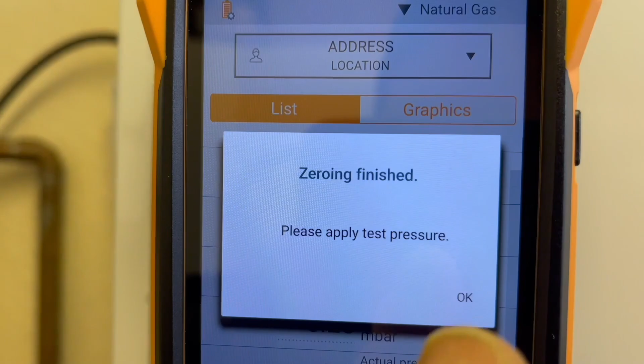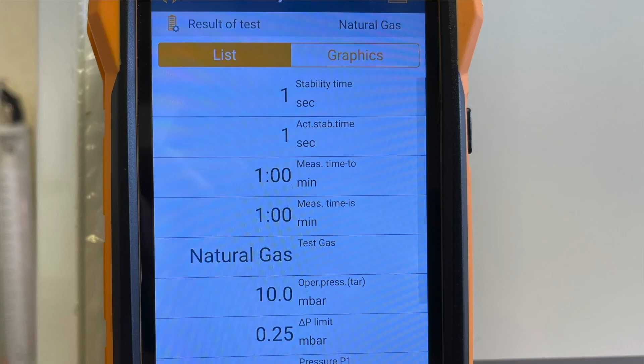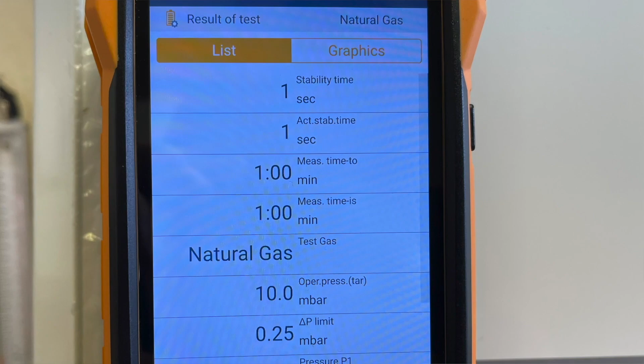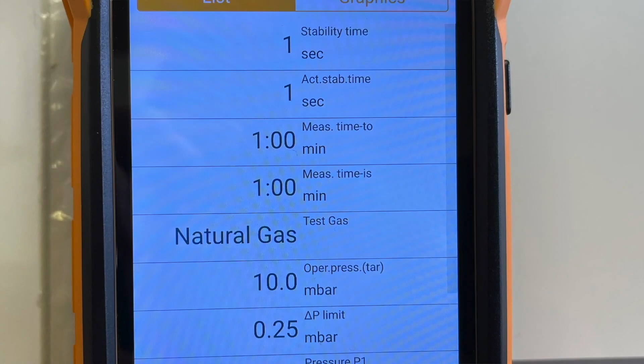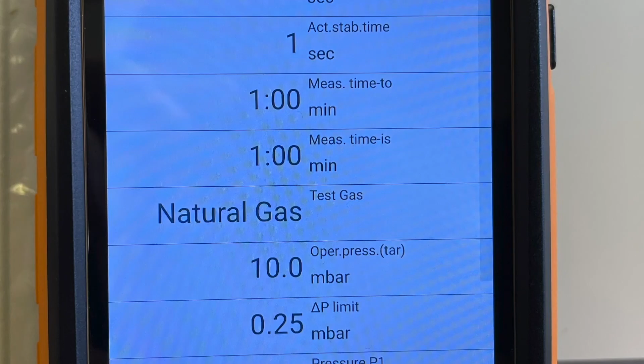There we go. Next thing I need to do now is put some gas into it. So we can see I have already set it to a duration of 1 minute. It's set on natural gas. It has a maximum operating pressure of 10 millibars, and it has a minimum of 0.25. So it's got to go between those pressures. And at the moment I've got it set at 0.